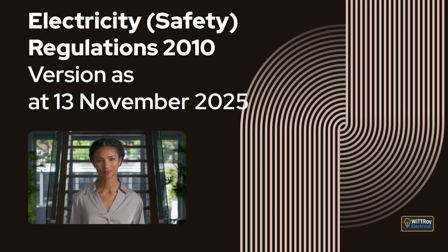Reg 89 use of handheld appliances in certain high-risk situations. This regulation explains that when a handheld appliance is used by a person who is immersed, partly immersed, or substantially conductive, the appliance must meet specific safety supply conditions. These include being fixed wired and supplied from a source isolated from earth with a voltage between conductors not exceeding 250 AC volts, being supplied from a safety extra low voltage source, or being double insulated and supplied through an RCD.